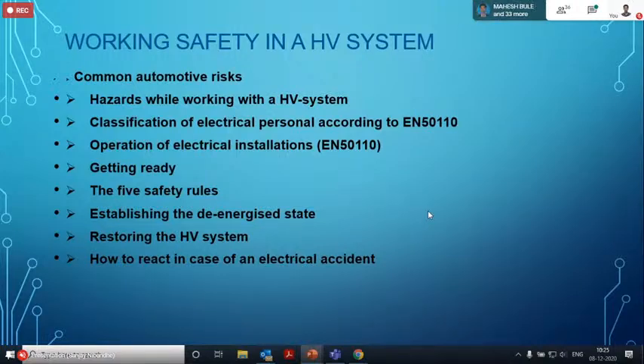At 72 volts, without protection, if a person touches the systems or any leakage happens through the wiring harnesses laid down on the body side, there is a lot of risk one has to face. With that type of risk, proper insulation coverings are defined on all electrical cables connected from battery to motor end or controlling ends. All those areas have to be properly channelized and protected, placed in conditions where no water or environmental effect happens to those cables. We have to really look at the risks, which are very high for such matters.